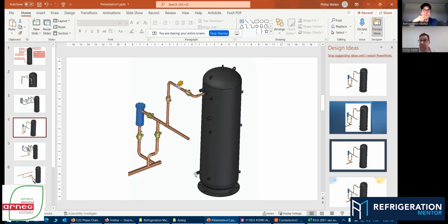We can still heat hot water. We do a lot of hot water heating out of that. We're not doing any heat recovery because there's not that much heat, but enough to gain more than a few degrees in the hot water for a customer. But you can pump her out. They're all loop designed, so there's no hot gas associated with those small systems, obviously. But you can pump out low temperature and keep that medium temperature running completely. So the low temperature is just isolated. And a good little convenience store application.